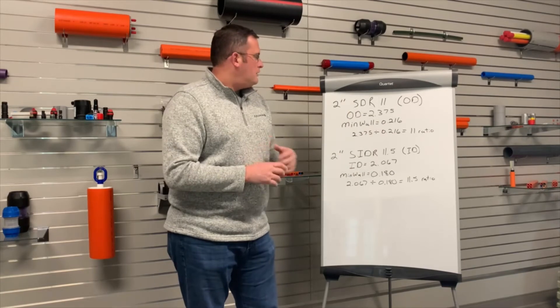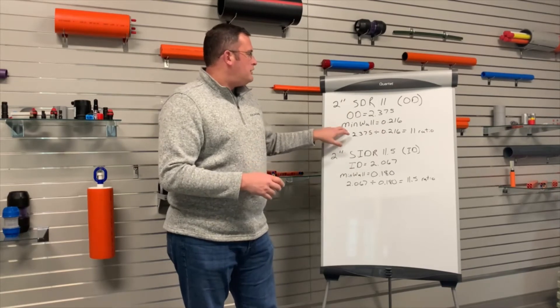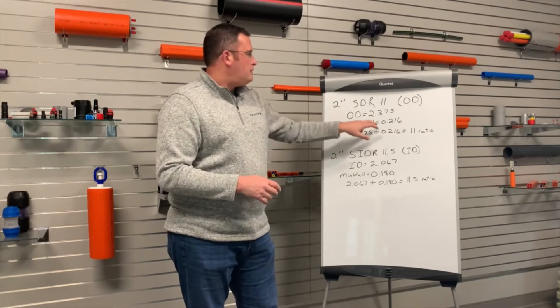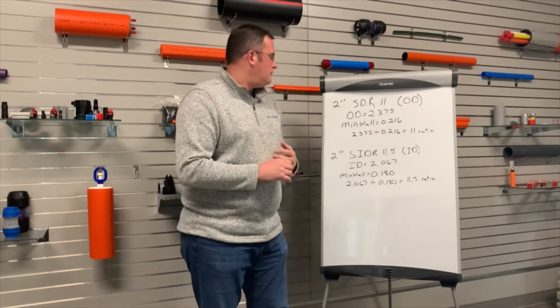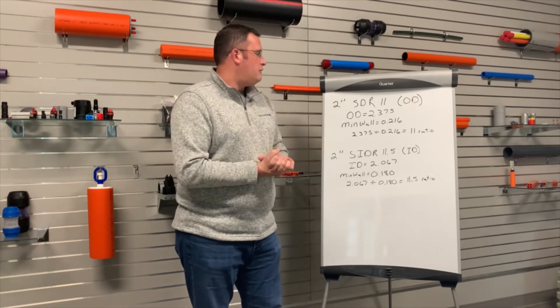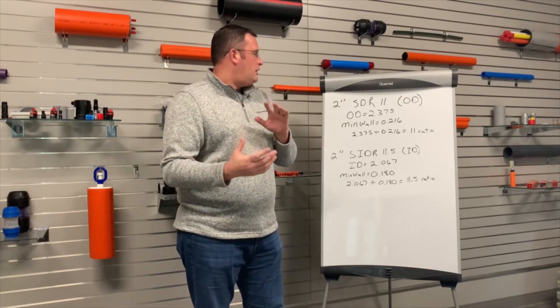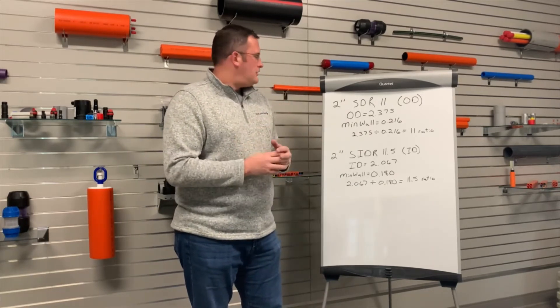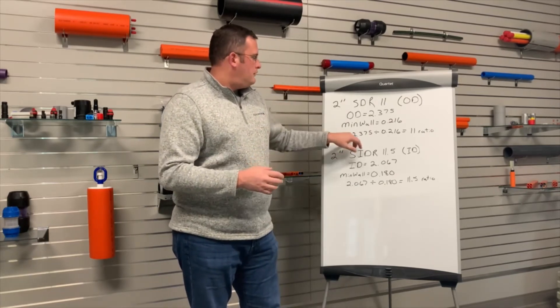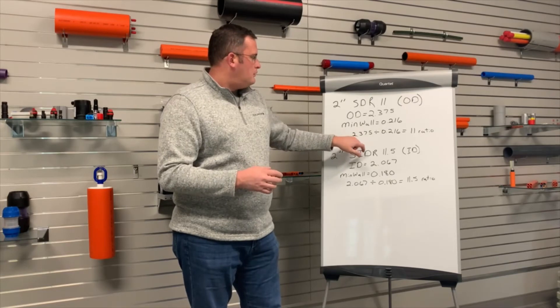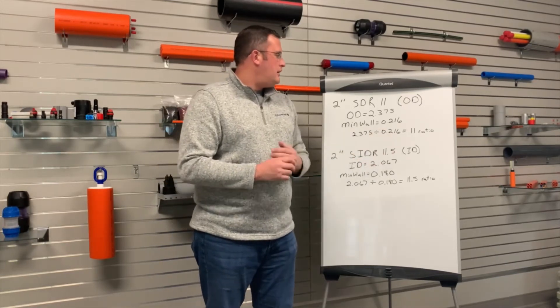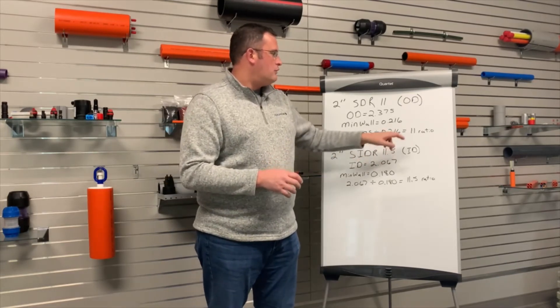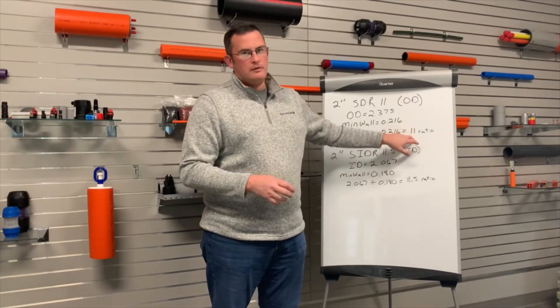The minimal wall thickness for that pipe is 0.216. Simply, the ratio of SDR 11 relates OD to wall thickness — OD 2.375 divided by the wall thickness gives you a ratio of 11.